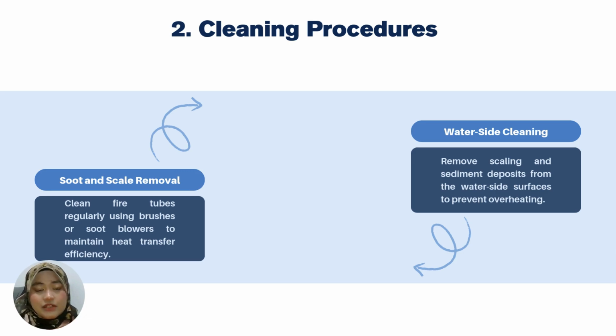Next, we have cleaning procedures. It can be done with soot and scale removal and also water-side cleaning. Soot and scale removal revolves around cleaning fire tubes regularly using brushes or soot blowers to maintain heat transfer efficiency, while waterside cleaning involves removing scaling and sediment deposits from the waterside surfaces to prevent overheating. Let's watch snippets of these videos.